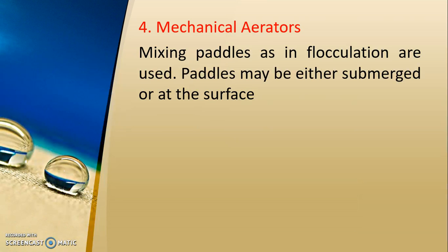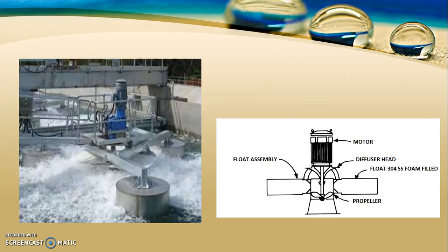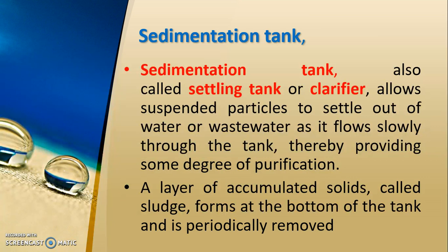Next are mechanical aerators, where mixing paddles — as in flocculation — are used. Paddles may be either submerged or at the surface, providing turbulence to expose water to the atmosphere. After aeration, water goes to the sedimentation tank, also called a settling tank or clarifier. Sedimentation tank allows suspended particles to settle out of water as it flows through the tank, providing some degree of purification. A layer of accumulated solids called sludge forms at the bottom and is periodically removed.